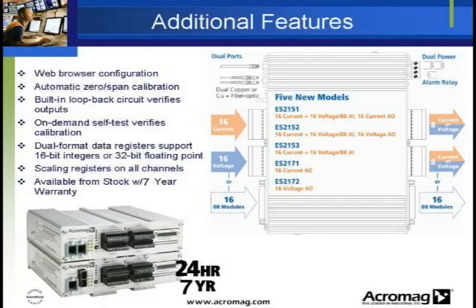Onboard calibration automatically calibrates instruments to perform better over temperature ranges. Built-in loopback circuit and on-demand self-test verify input and output calibration for accurate measurements. User-configurable 32-bit floating point scaling registers ease the processing demands of PLC, DCS, or CPU controls. Dual-format data registers support both 16-bit signed integers and 32-bit floating point formats.